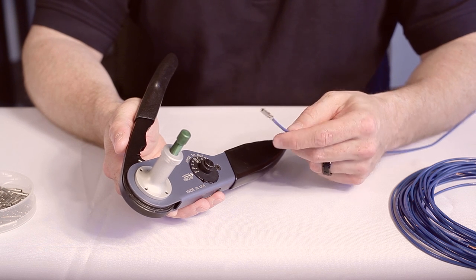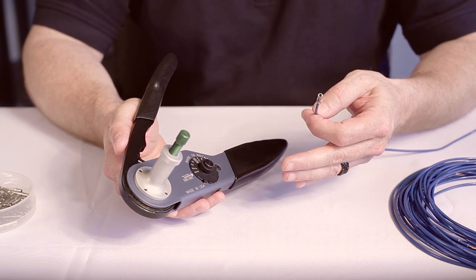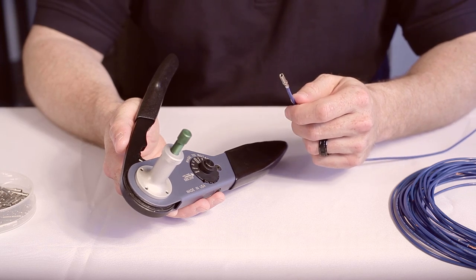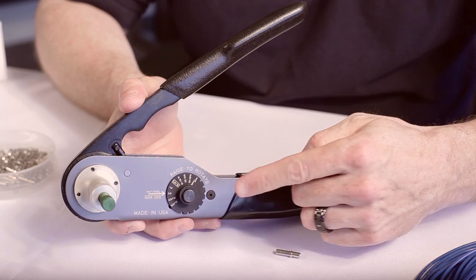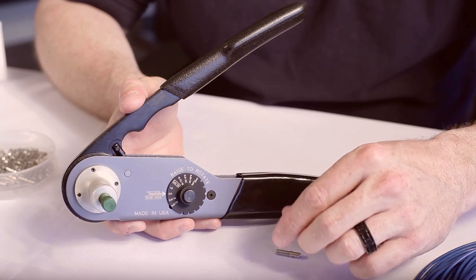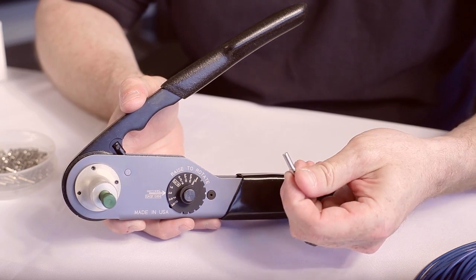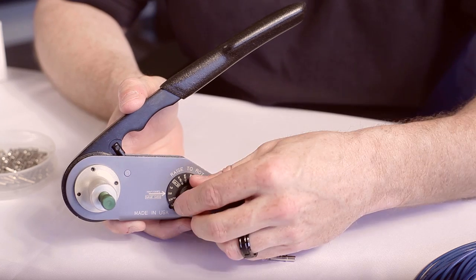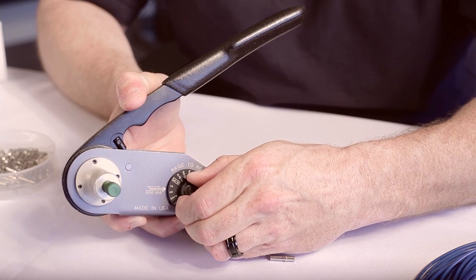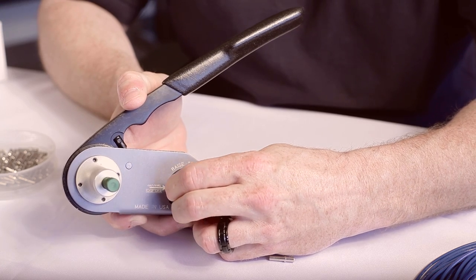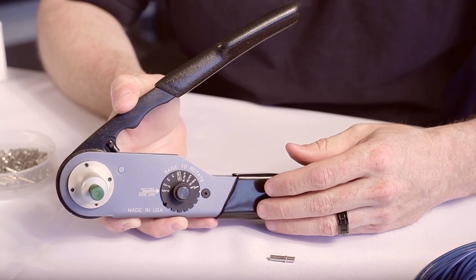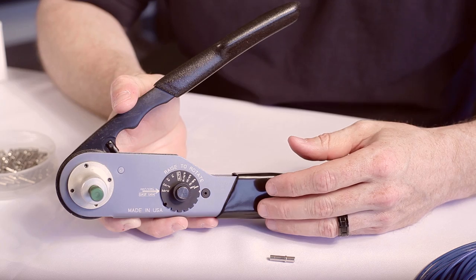With just a few quick settings, you can be making quality crimps quickly and consistently. The first step in using the tool is to set the contact size dial to match the size contact that you want to crimp. Just lift it up and turn it so the contact size lines up with the indexing mark on the tool. The dial will drop down and lock in place at your chosen size.